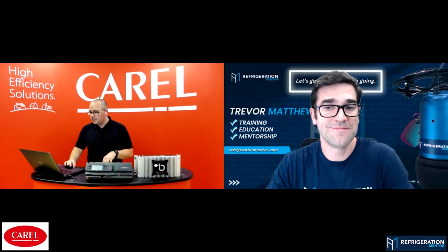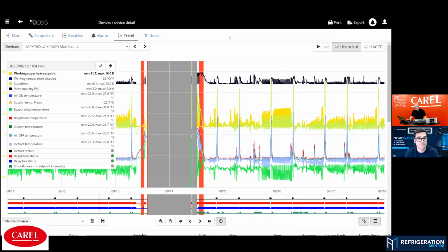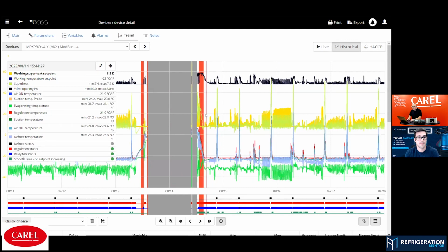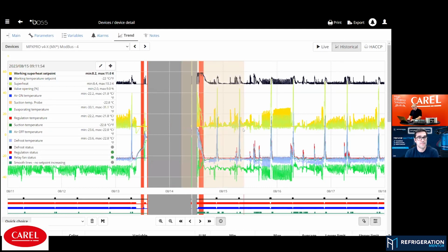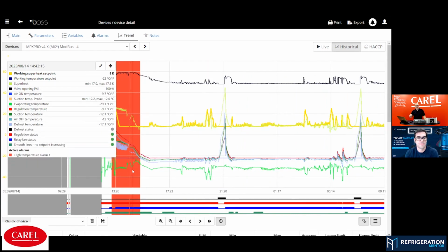Let's jump into one of the other cold rooms. Okay. And the pro cold room. That looks great. We should be on the right side. Same plant. Low temperature cold room. Everything was running more or less, but now we saw a high temperature alarm. We were still monitoring this application, so it was quite strange. We had the high temperature alarm on only one cold room, and all the other cold rooms were running.